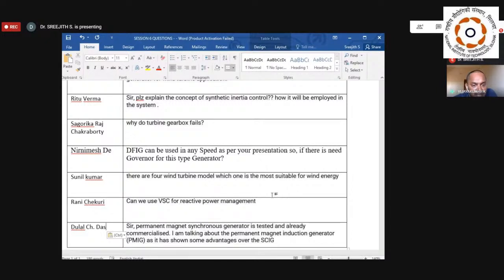Another question is: DFIG can be used at any speed as per your presentation, so is there no need for a governor for this type of generator? It's not required. There is no concept of a governor for these generators, because wind keeps on changing. We cannot control the speed of the wind turbine, since by nature the wind velocity is changing. For controlling the speed of the wind turbine, you can go with generator control or pitch control. That's enough.